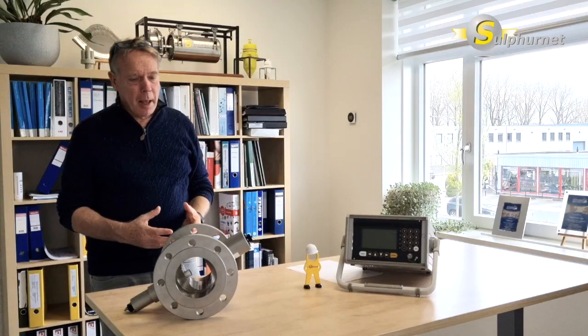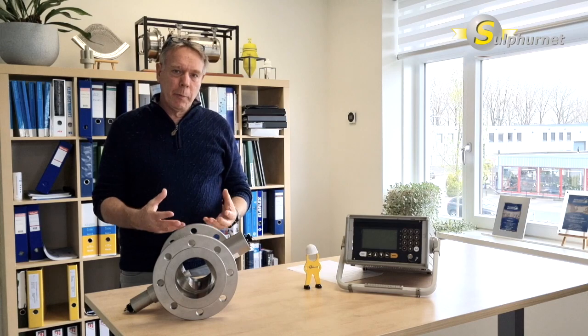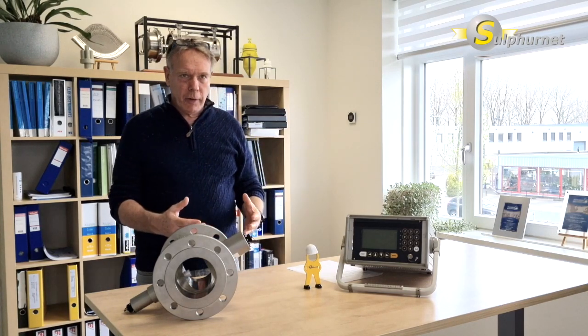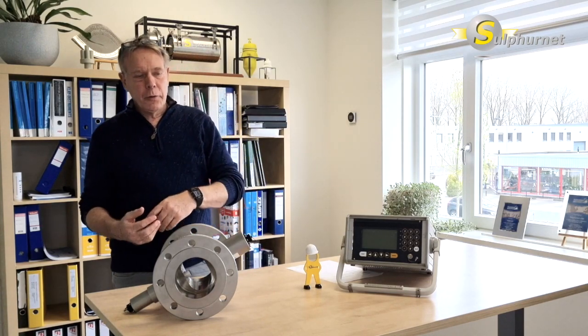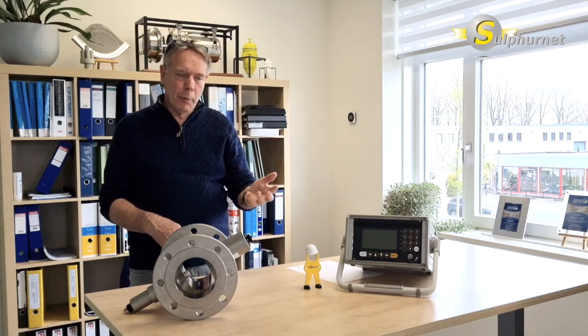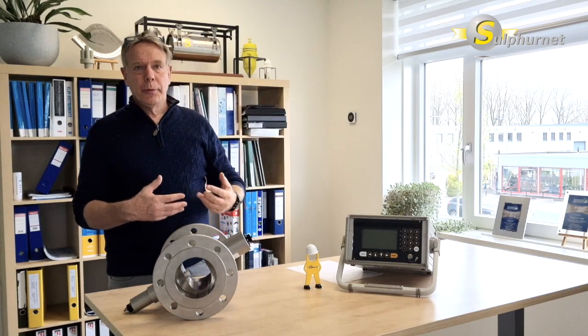The best way to position the Turbidity Analyzer is to put it on the outlet side of the pressure leaf filter, this horizontal tank filter, and before the polishing filter. This will give you the possibility to measure the ash level, and if you exceed it you can put the filtration process in a loop, and based on the loop you can check if the ash level is going down again or whether you have to stop the plant.